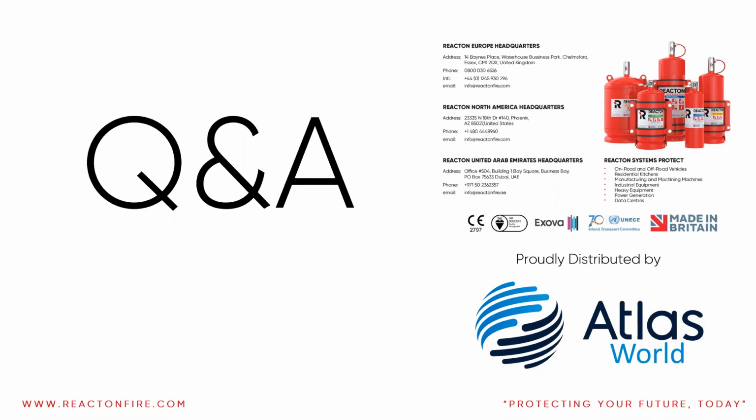Absolutely. Sarah has asked what size of space can be covered by this system. Ed has responded there, it obviously depends on the agent being used. But for example, with the direct clean agent systems, 1 kilo will cover 1 cubic meter. Yeah, exactly. So, we have quite a lot of options of cylinders. We start with a 1 kg system, a 2 kg, a 4, a 6, a 9, and an 18. But the great thing about the Reacton system is that the cylinders can be linked.